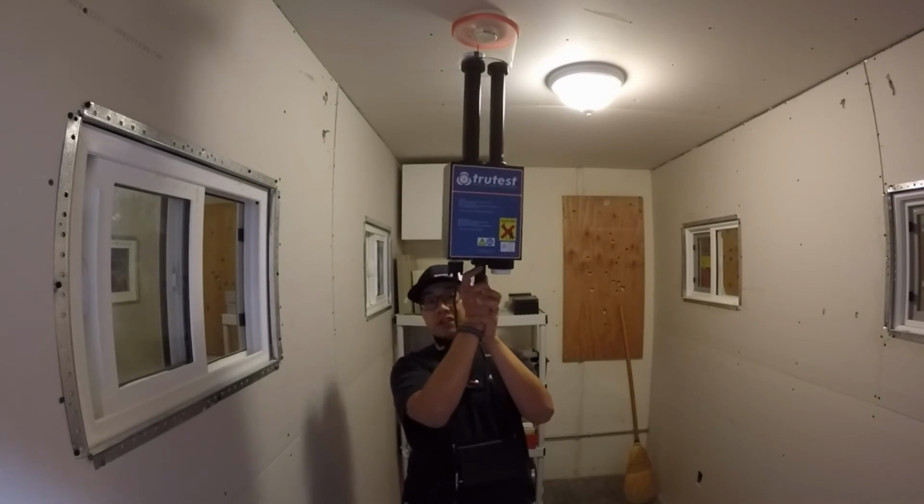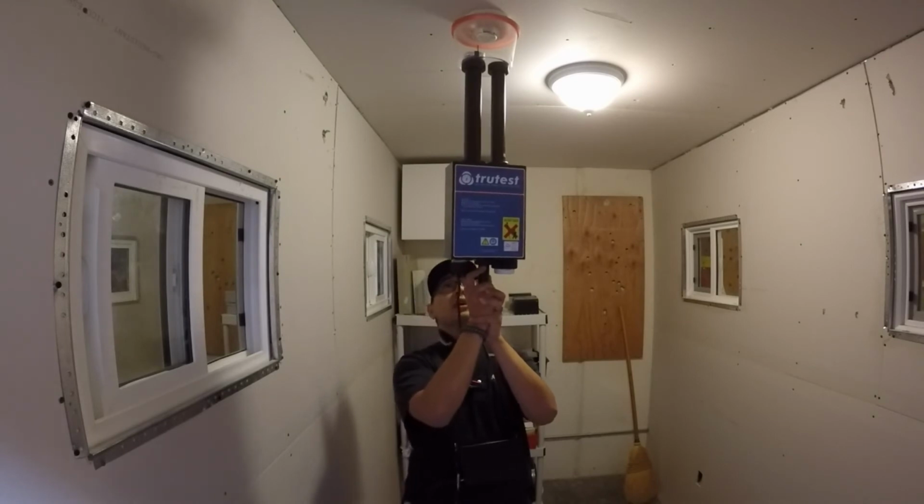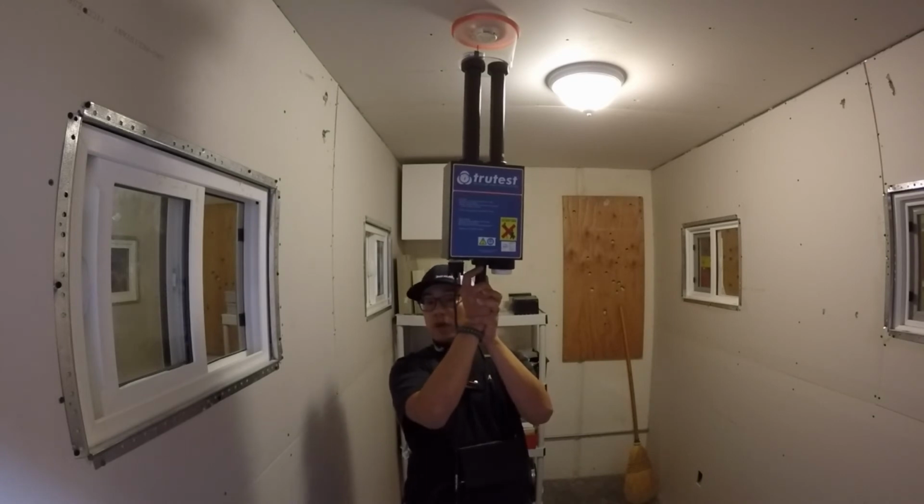So we're just going to hold this, could be for a few minutes, so it's good. It's a good workout. We'll know that the smoke detector is in alarm because the sounder will trip. So right now it's at 1.34%. It's within the range. The minimum, again, for this smoke detector is 1, and the max is 4%. And you can find that information on the back of that smoke detector head.